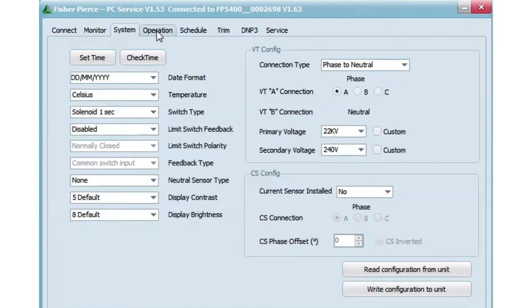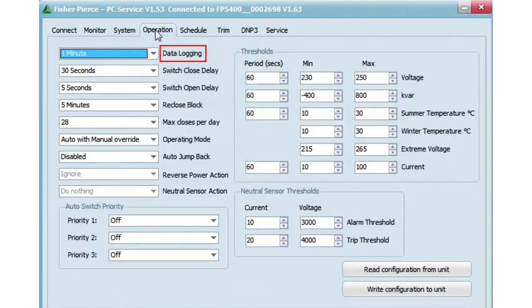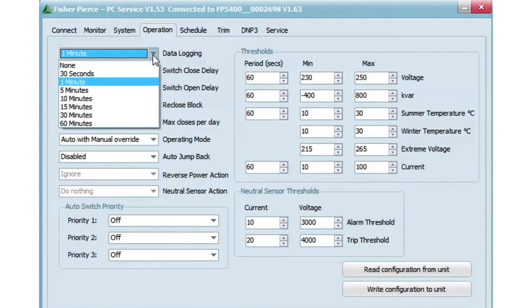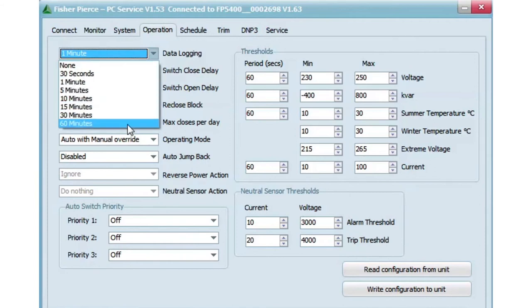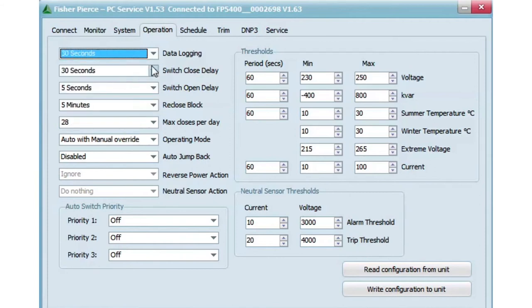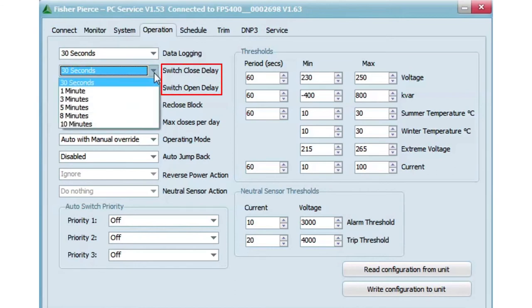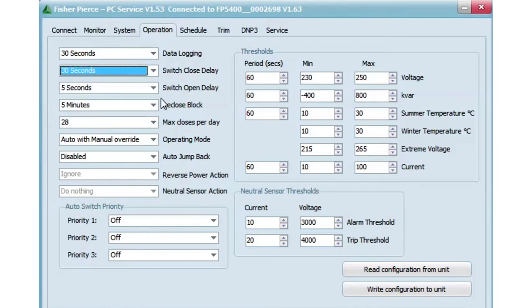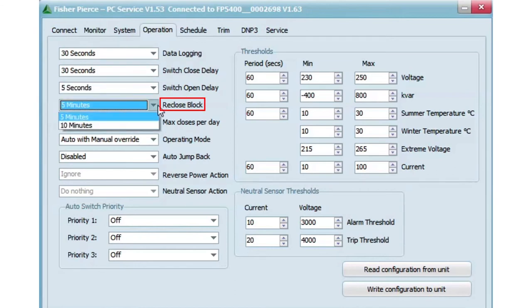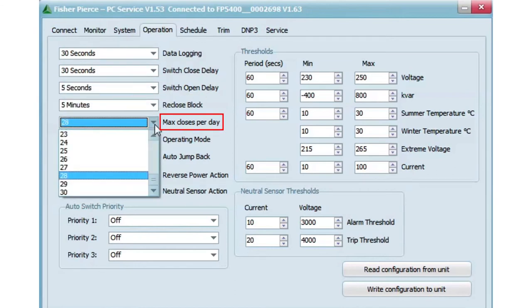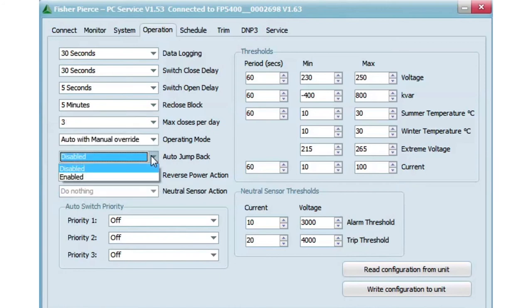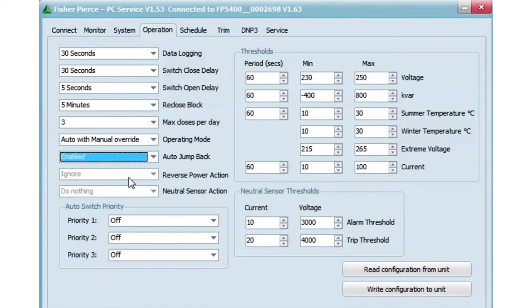Operations include data logging, with 128 kilobytes of memory, equivalent to 10,000 data logs. Different switch setups, re-close blocks, and maximum closes set per day. The auto jump back feature ensures that if the unit is left in manual mode, at the end of the day the unit will automatically jump back to auto.